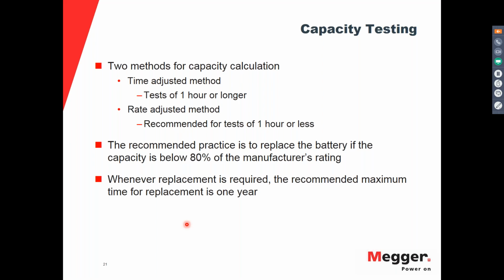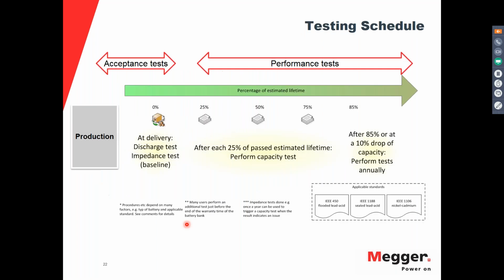The reason for this, again, remember I already mentioned the capacity of the battery will have a knee point where it starts dropping faster as it ages. So there's not too much time to make any correction or to replace the battery, so you should start working on this soon. So here's the example or the slide that depicts the testing schedule.